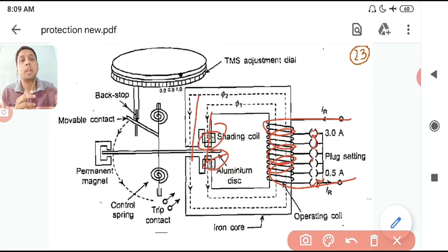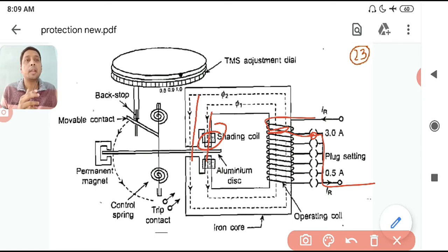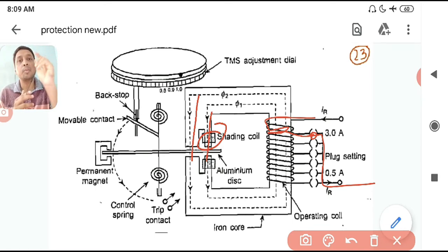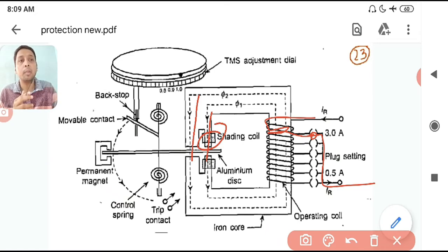You can remove one plug and connect it as you proceed to the upper portion — your plug setting increases. Going to the upper portion means you are reducing your turns. If you put it at 3, you have only one or two turns and then it directly connects. If you reduce the plug position, you are getting more turns. Going up gives small turns — this is how we set the threshold current.